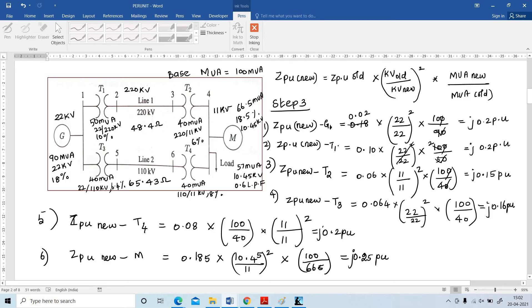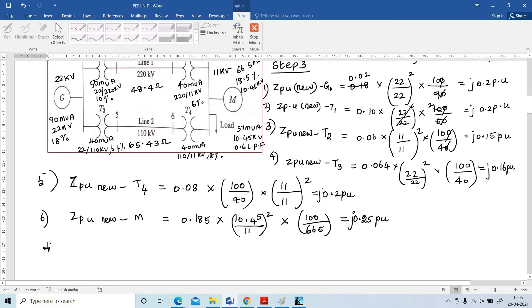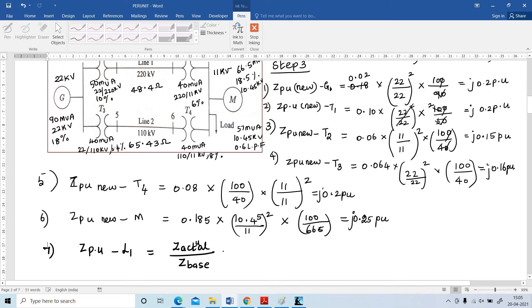All per unit values for generators and transformers are complete. Next, find ZPU for transmission line 1. ZPU = Z_actual / Z_base. Z_actual = 48.4 ohm. Z_base = V² / P = (220)² / 100 = 484 ohm. ZPU = 48.4 / 484 = 0.10 per unit.